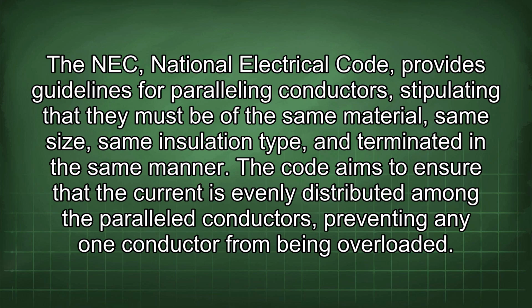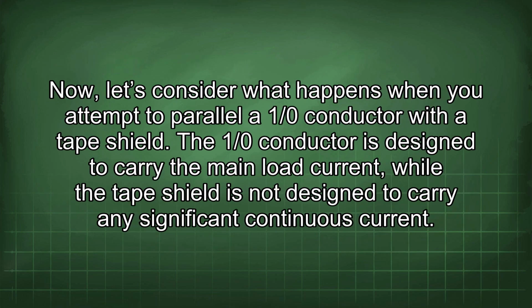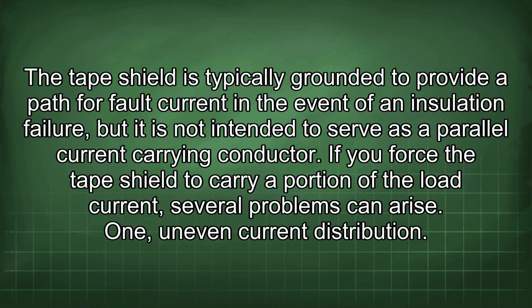Now, let's consider what happens when you attempt to parallel a 1/0 conductor with a tape shield. The 1/0 conductor is designed to carry the main load current, while the tape shield is not designed to carry any significant continuous current. The tape shield is typically grounded to provide a path for fault current in the event of an insulation failure, but it is not intended to serve as a parallel current carrying conductor. If you force the tape shield to carry a portion of the load current, several problems can arise.